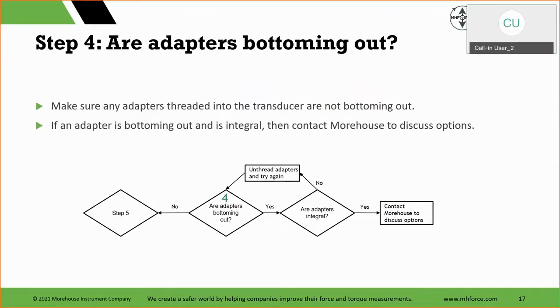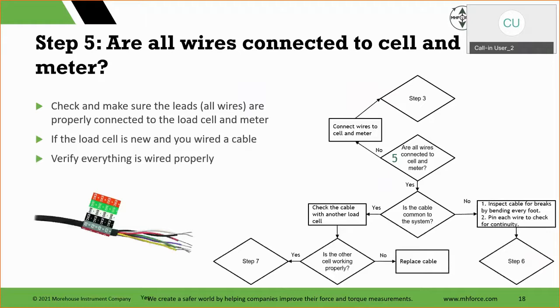We had one load cell that just wasn't performing in compression and great in tension. That's usually a sign that an adapter is bottoming out. If it performs great in tension and then in compression the output plateaus, that's a sign. The one we had that was problematic had dust and dirt in it. And again, that was from something a customer did. They took everything out, took it apart, and when they got it back together, we found some dirt in there because they didn't blow it out.